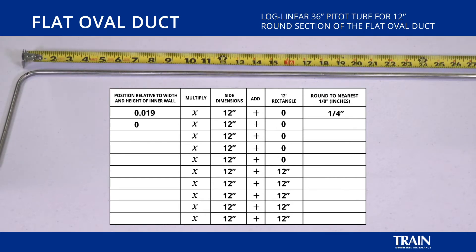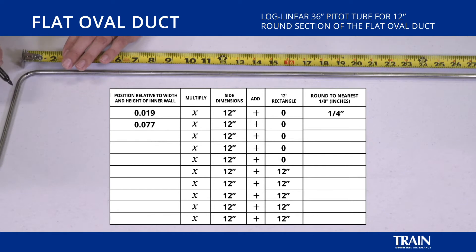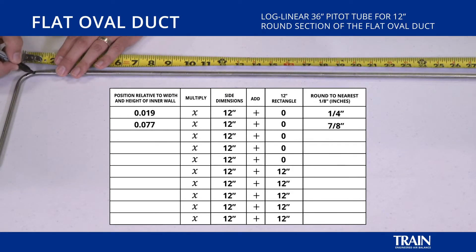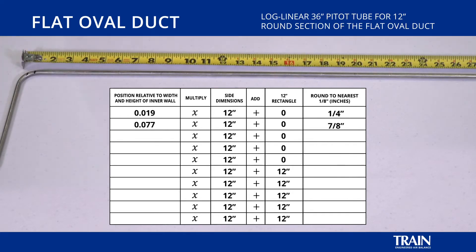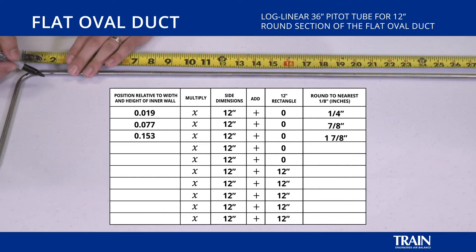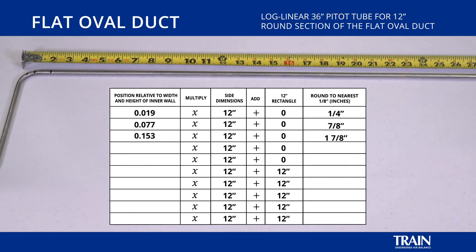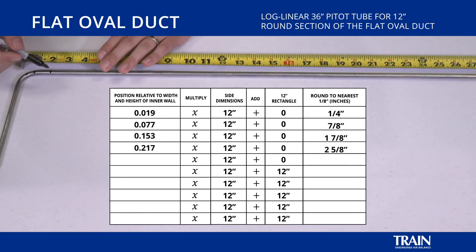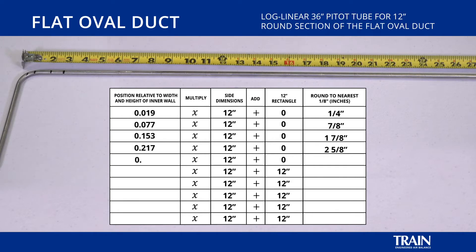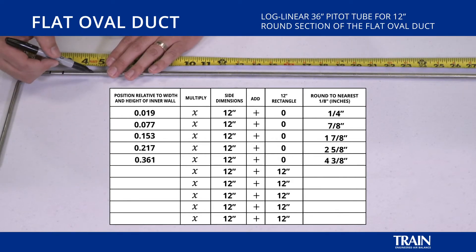The second factor, 0.077, results in seven eighths on our pitot tube. The third factor, 0.153, results in one and seven eighths on our pitot tube. The fourth factor, 0.217, results in two and five eighths on the pitot tube. The fifth factor, 0.361, results in four and three eighths on the pitot tube.